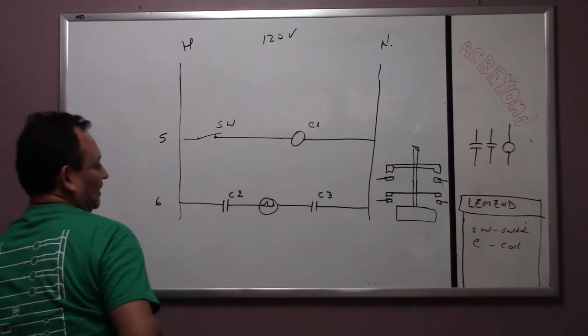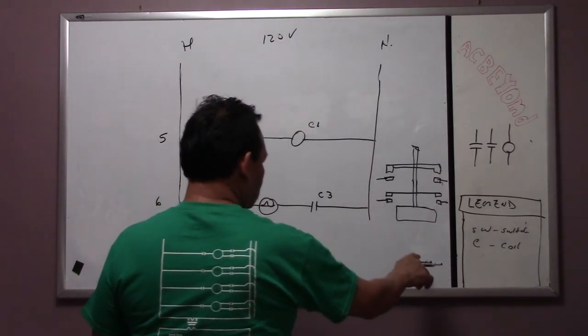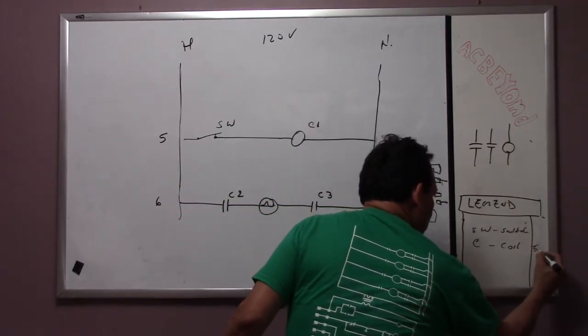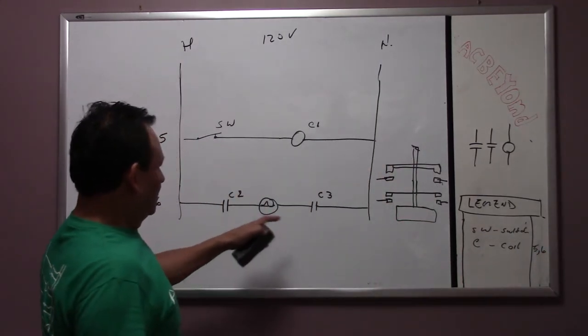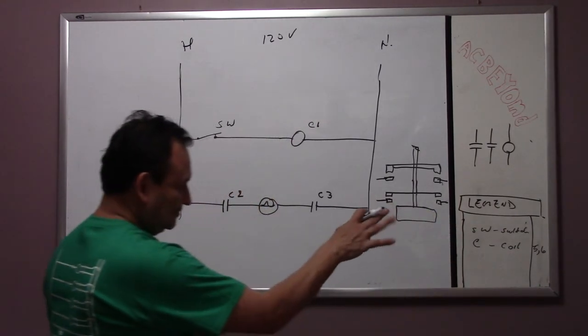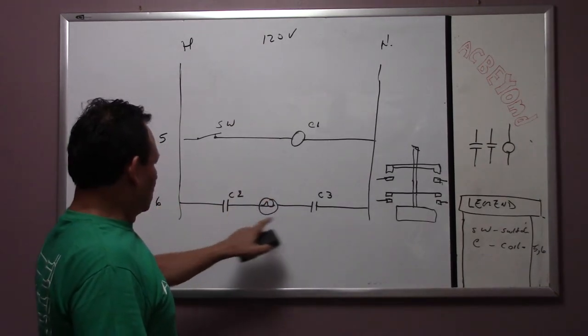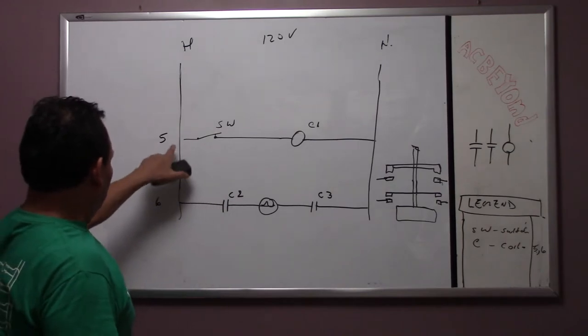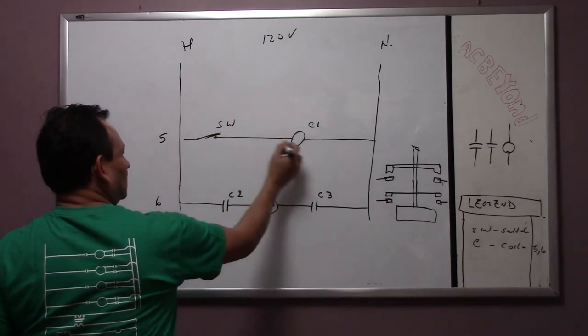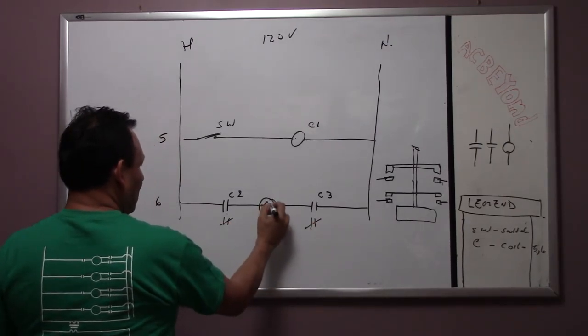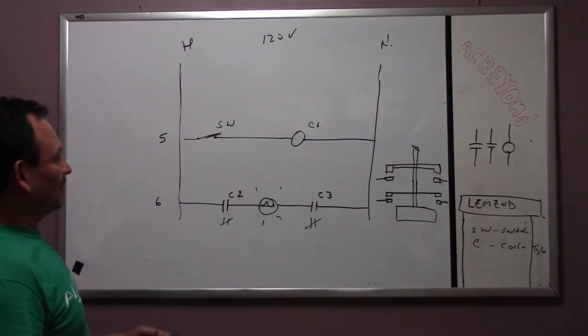Let's say this is line five and this is line six. On the coil, on the side, it's going to say five and six — meaning the coil itself has two contacts, one on line five and one on line six. So when this switch closes, the coil energizes, closes these contacts, and the light bulb is going to light up.